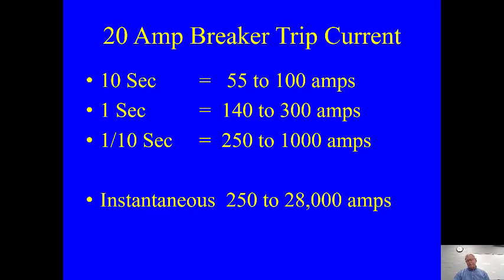But if that breaker trips instantaneously, you can have anywhere from 250 to 28,000 amps going through that breaker with number 12 gauge wire. So now you're really heating it up, and these are what you call molded case breakers. Whenever you have an instantaneous fault, ground fault or short line to line, they are designed to explode or disintegrate as a last-ditch attempt to interrupt that circuit where the fault's at from the power source. So that's part of what's designed into them, and they're made to blow up, and I've known them to do that.